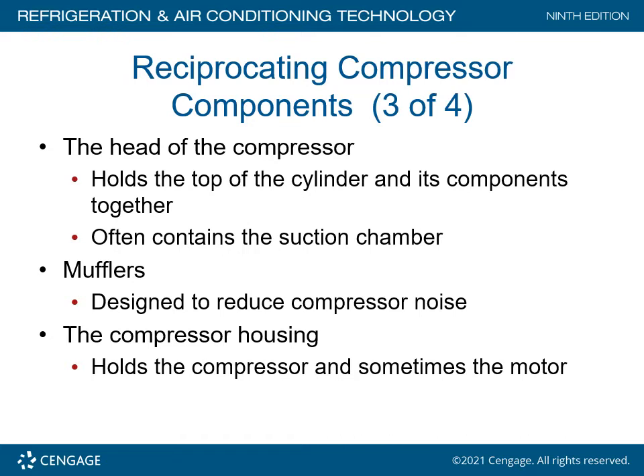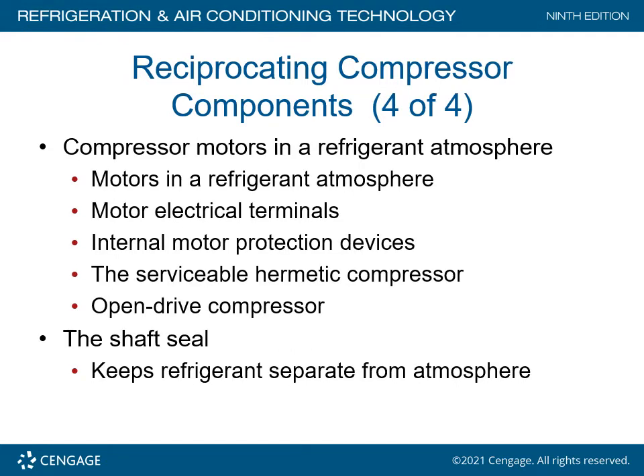The head of the compressor holds the top of the cylinder and its components together, and often contains the suction chamber. Mufflers are designed to reduce compressor noise — that's all they're designed to do. Mufflers are not the same thing as vibration eliminators. The compressor housing holds the compressor and sometimes the motor. In hermetic designs, motors operate in a refrigerant atmosphere and have motor electrical terminals and internal motor protection devices.